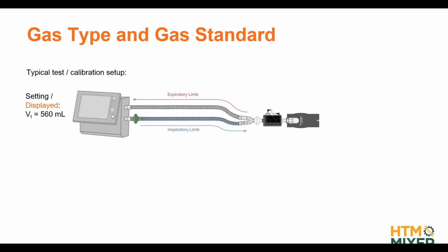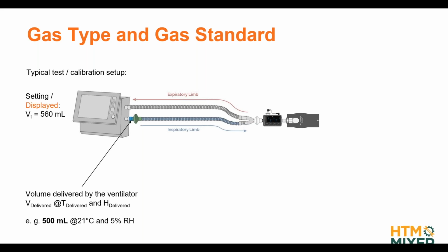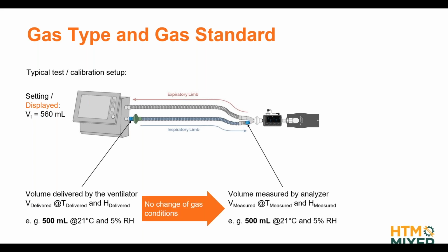So here, explained again, we have a setting of 560 milliliters on the ventilator. However, we know that because it's in BTPS, it's going to under-deliver in volume. And because there is no change of the gas conditions, the same amount of volume is then going to arrive at our analyzer. And again, if that analyzer is set to ATP, it's going to measure the 500 milliliters that actually goes through the flow channel here and ends up at the test lung.